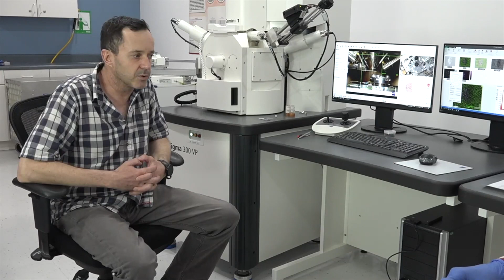We've got various different detection systems on this. A lot of options, such as variable pressure, which allows you to work with uncoated or non-conductive samples, which is not something all instruments can do. So different detection systems: secondary electron detection, backscatter electron systems, and then also X-ray, so energy dispersive capabilities, which can give you compositional, elemental information. So basically it tells you what is in the sample and how much of certain elements are in the sample. So overall, a very nice, complete, functional system. Yeah. Very nice, very nice.